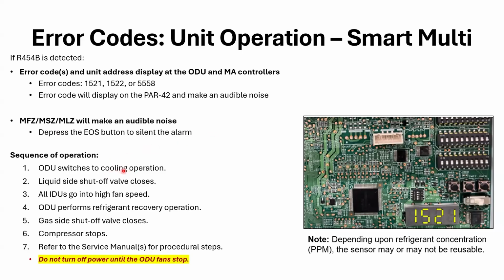Sequence of operation: the outdoor unit switches to cooling operation. The liquid side shut off valve closes, right? This is basically like a pump down, the same thing you do in pump down mode, but it's doing it automatically. All indoor units go into high fan speed. The outdoor unit performs refrigerant recovery operation. The gas side valve will shut when it gets down to, the note I have on that is it'll run down to 22 PSI on the low side. Then it's going to shut the gas side valve, because if we're leaking, we don't want to go down below that and suck air into the system, right? If we pump it down and there's a leak, and we go down to 0, we're pulling air into the system, mixing it with that refrigerant, and then we just lost all the charge we pumped down into the outdoor unit. So it's going down to 22 PSI.